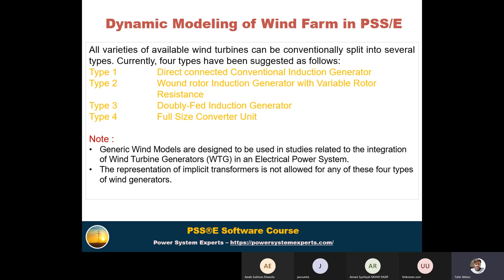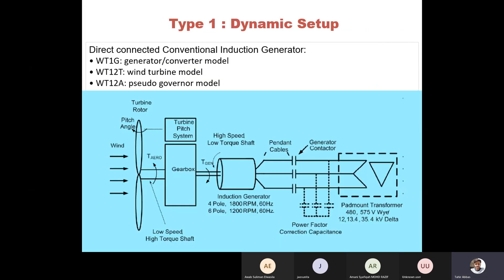An important note is that representation using an implicit transformer is not allowed for any of these four types of wind generators. You need to model them with explicit behavior — from the low voltage (LV) through to the medium voltage (MV) and high voltage (HV). In implicit modeling you can model the generator directly at the HV bus, but for wind generators you must model explicitly from LV through the GSU transformer to medium voltage and then step up to high voltage.